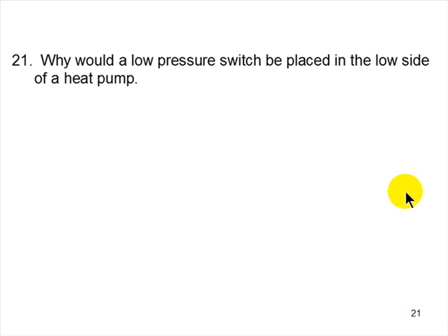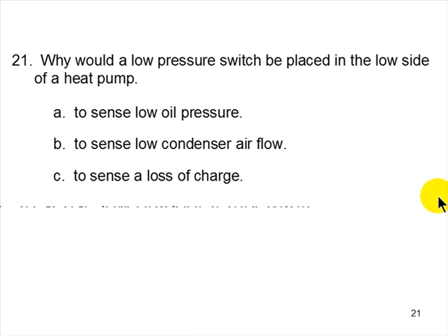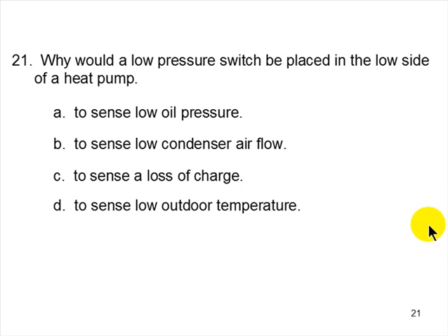21. Why would a low pressure switch be placed in the low side of a heat pump? To sense low oil pressure? To sense low condenser airflow? To sense a loss of charge? Or to sense low outdoor temperature? What do you use a low pressure switch for? Yeah, check loss of charge, which is low pressure.